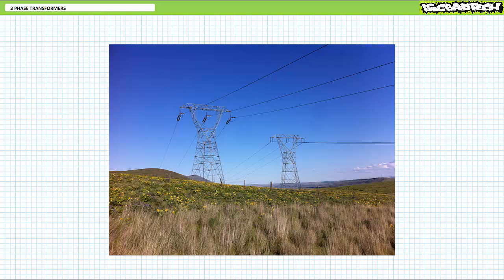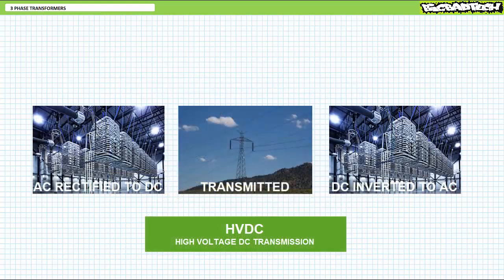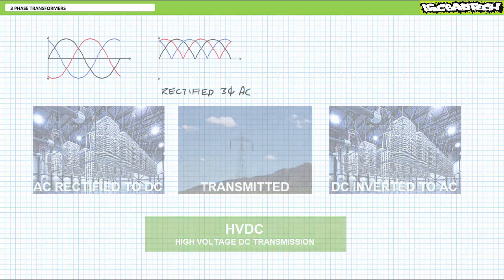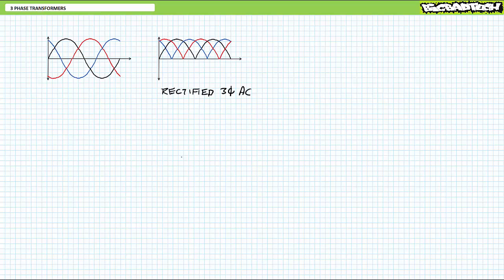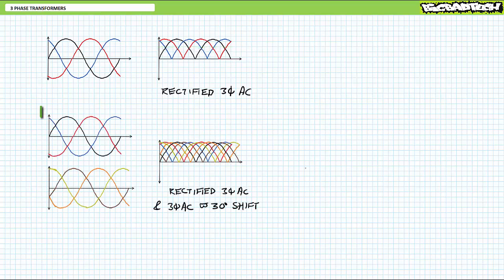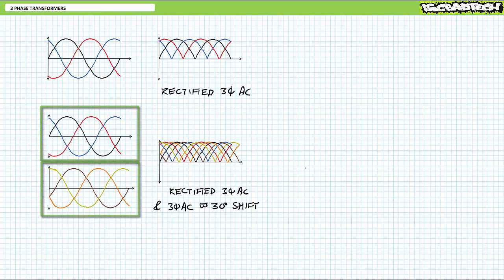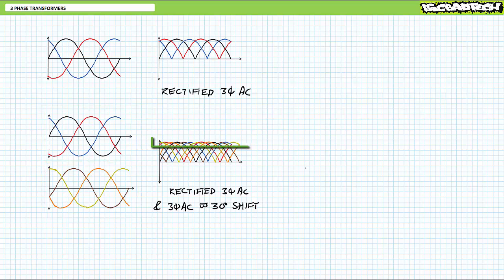Lest you think that phase shift is only important to AC applications, phase shift has other important applications inside high voltage DC transmission, which is essentially the large-scale rectification of AC to DC, transmittal over long distances, and then the subsequent inversion of DC back to AC at the point of use. Given ordinary rectified three phase AC on the DC link, there's a noticeable ripple which may cause unwanted harmonics. However, rectifying the original unshifted AC along with the output of a Y to delta transformer with a 30 degree phase shift, it noticeably smooths out the rectified result such that much, much less ripple is observed and result in harmonics reduced. We'll examine this and many other applications of three-phase transformers in later lectures.